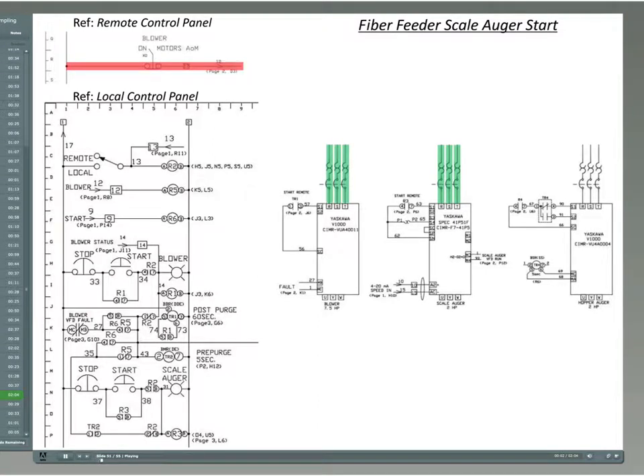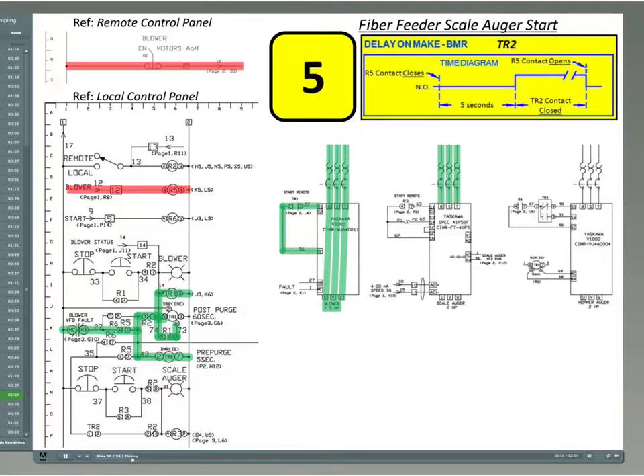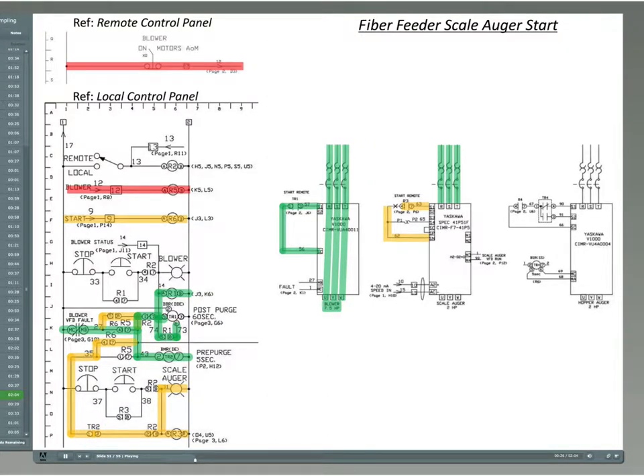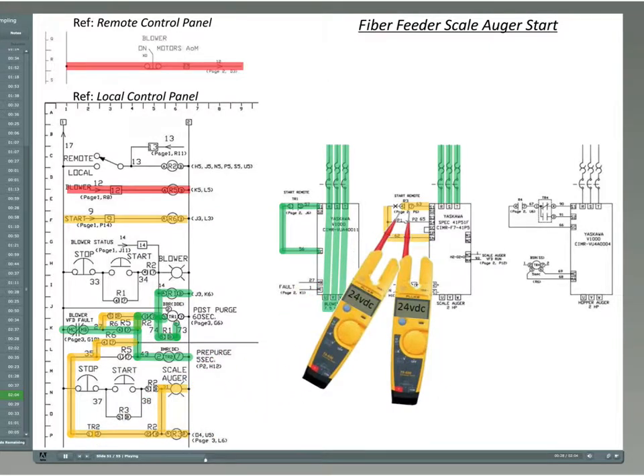TR2 is the delay on make (BMR) operation. The local remote switch on the local control panel is set to remote. The sequence is started when the operator selects blower on at the remote control panel. Relay R5 is now energized. Timer TR2 is enabled by the closed normally open contact of R5, and the time delay period for TR2 starts. Since TR2 is a delay on make (BMR) timer, its normally open contact remains open during the time delay period.